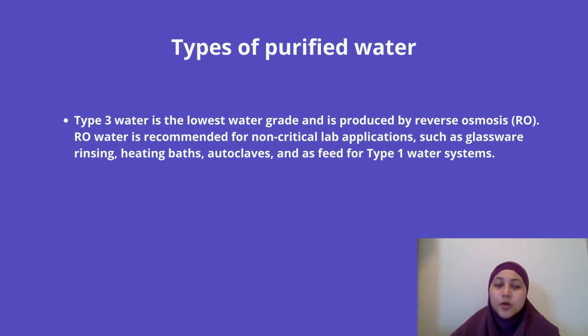Next is the type 3 pure water. The type 3 pure water is the lowest grade of pure water, and it is produced by reverse osmosis. The type 3 pure water is normally recommended for non-critical lab applications such as glassware rinsing, heating bath, autoclave, and as feed for type 1 water system.